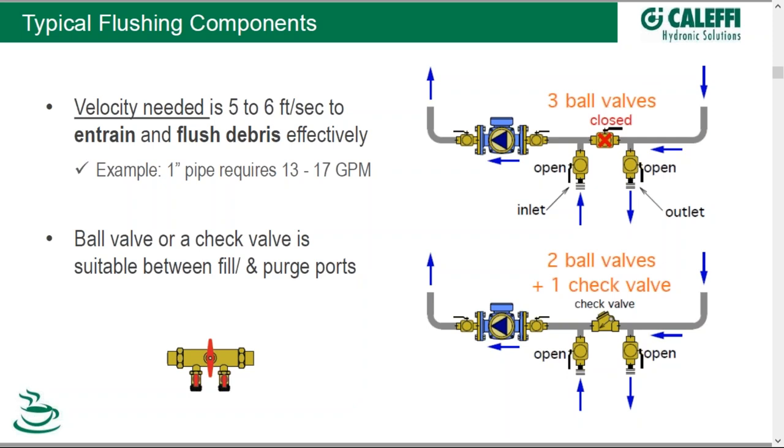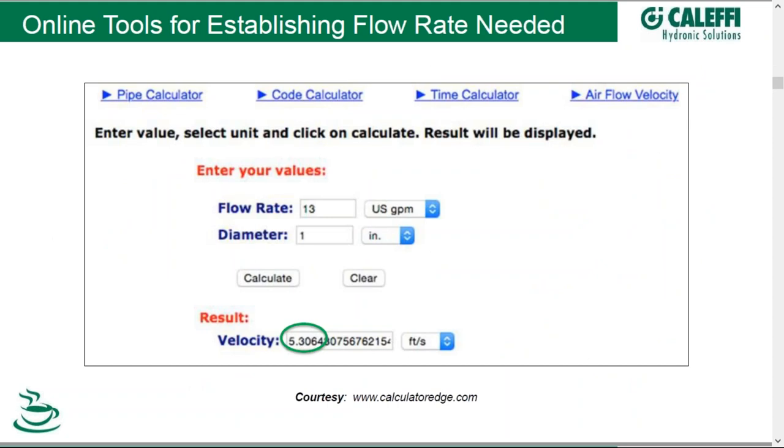When it comes to flushing debris, the velocity needed in a pipe is about five to six feet per second average pipe velocity to do a good job of entraining and burping that debris out of the system effectively. As an example, a one-inch pipe will require anywhere from 13 to 17 gallons per minute approximately. Some manufacturers such as Caleffi offer a fill-purge valve that's all one piece, which is convenient. Online calculators can answer the question quickly — you want five to six feet per second, you have a one-inch pipe, and you can see that 13 gallons per minute through that one-inch pipe will give you the needed velocity.